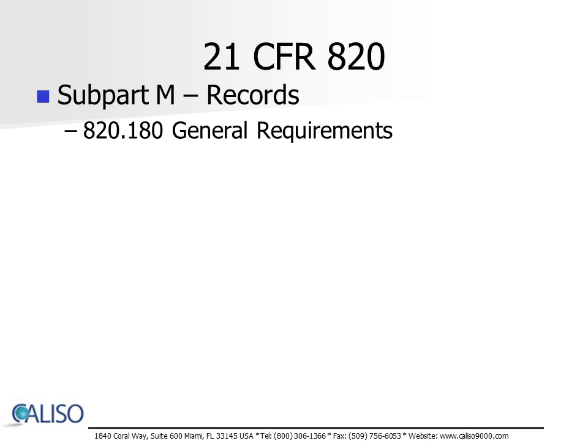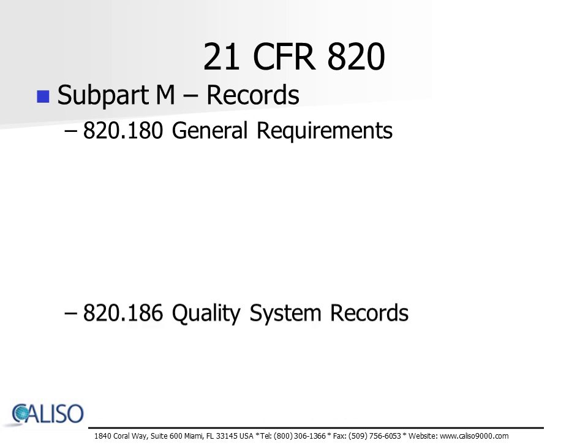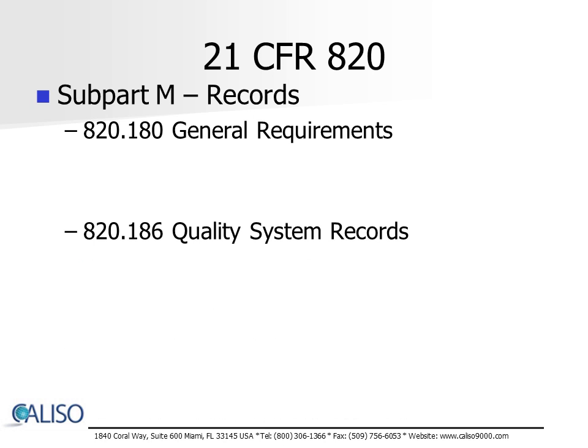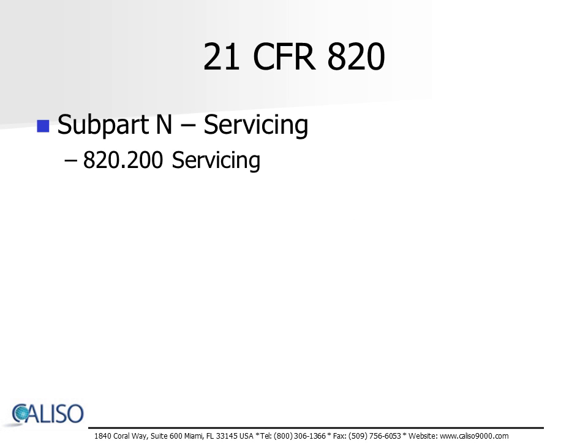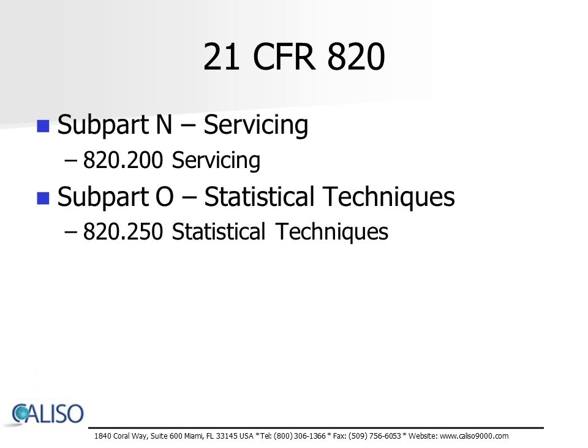Subpart M contains the requirements for records, which includes the requirements for all quality records and their accessibility to regulatory personnel, device master records, device history records, as well as complaint files. Subpart N contains the requirements for servicing of a medical device, if applicable. Subpart O contains the requirements for statistical techniques for controlling and verifying the acceptability of process capability and product characteristics.